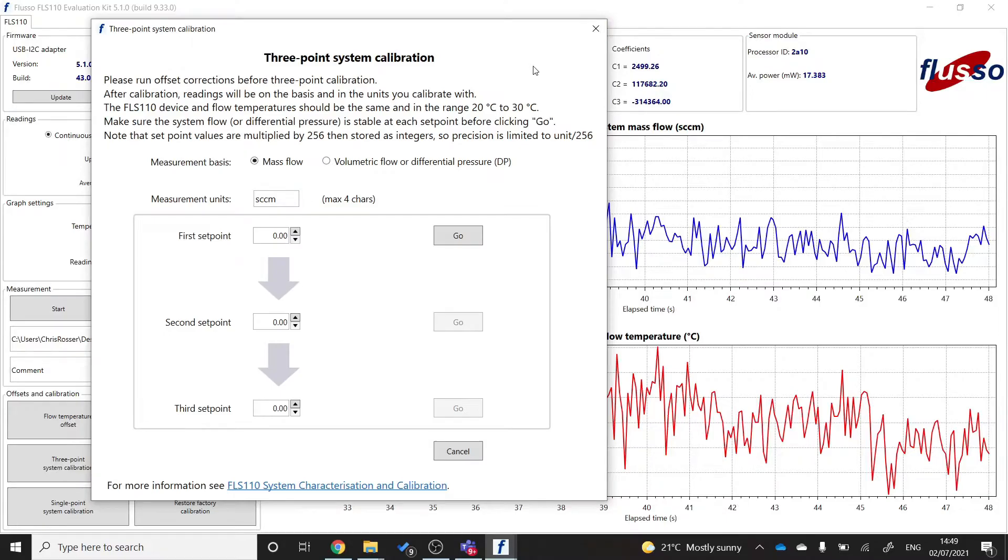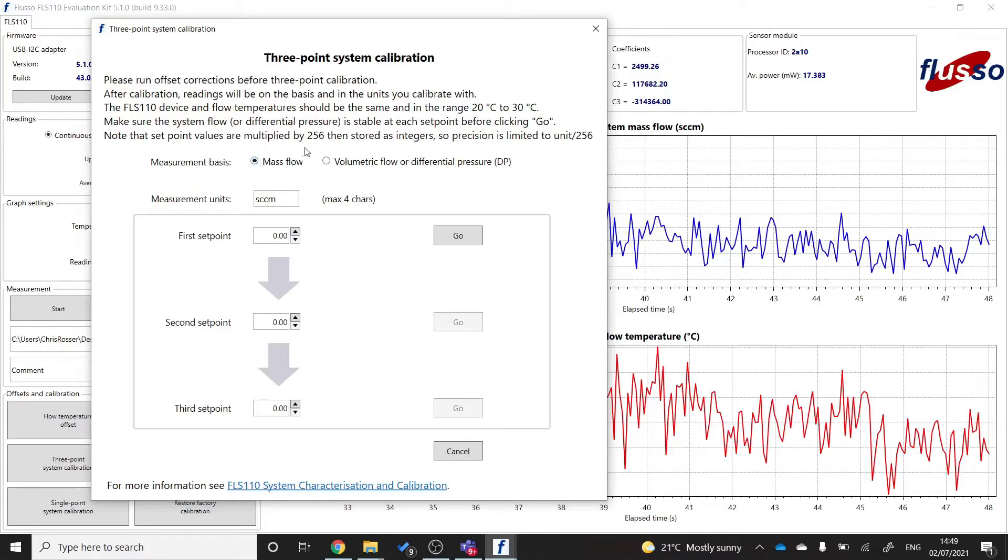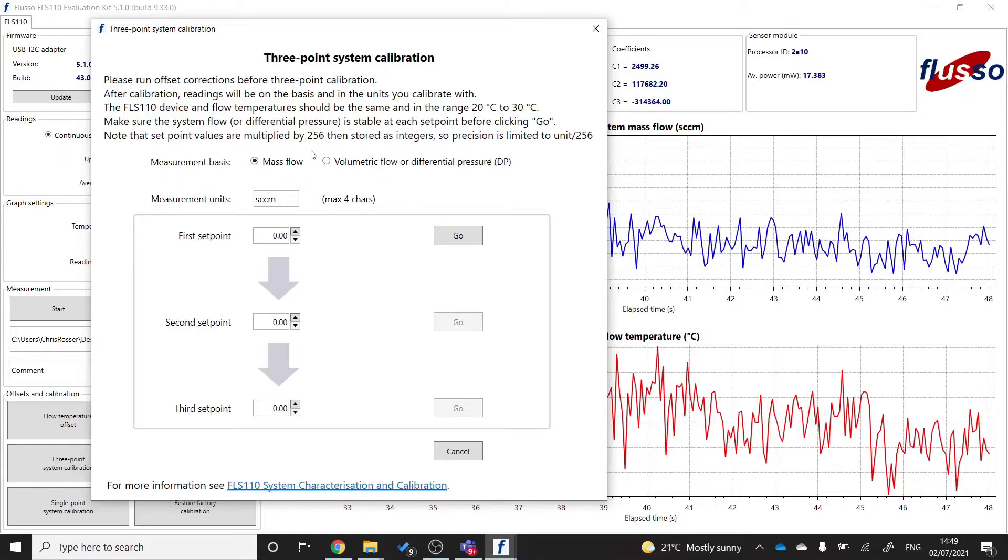And then the final step is to do a three point system calibration. This will set all of the coefficients in the firmware to the correct values for your system. Now, to do this, there are a few different options that you will need to go through. The first is to choose your measurement basis. Now, if you're looking to measure mass flow, you can select this mass flow measurement basis here. If you're measuring volumetric flow or differential pressure, you'll want to be selecting this one here. I want to measure in SCCM, which is a mass flow unit, standard centimeters cubed per minute. So I select mass flow.